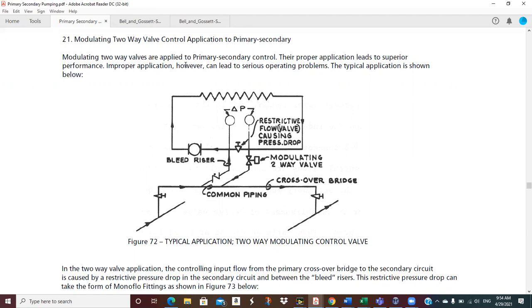Okay, so the way we make this work is, we've got our secondary, we're going to circulate it. We got our primary or crossover, we got our bleed riser and bleed return, and we're going to put a two-way valve here, and we're going to put a balancing valve up here, because when this valve opens, we have to have a pressure drop across the primary to force flow up into the secondary. If you don't, you won't get anywhere close to the proper amount of flow. So this thing gets balanced with this open so that we get the desired flow from the crossover into the secondary. So that's what is supposed to happen.